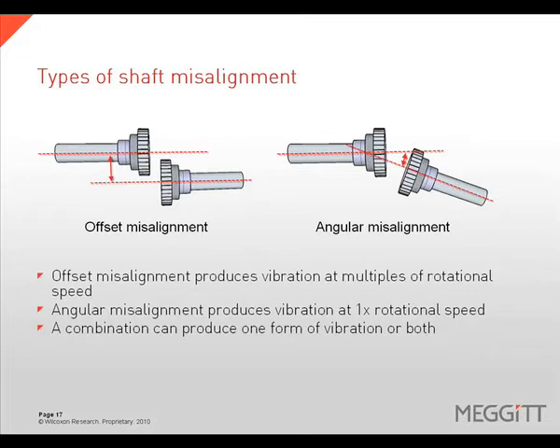There are two types of misalignment: offset or parallel misalignment, and angular misalignment. Offset misalignment will commonly produce a vibration response at multiples of rotational speed — 2 times, 3 times, 4 times, and 6 times are all common. Angular misalignment will commonly produce a vibration response at 1 times rotational speed, with the axial direction often being the highest in amplitude.